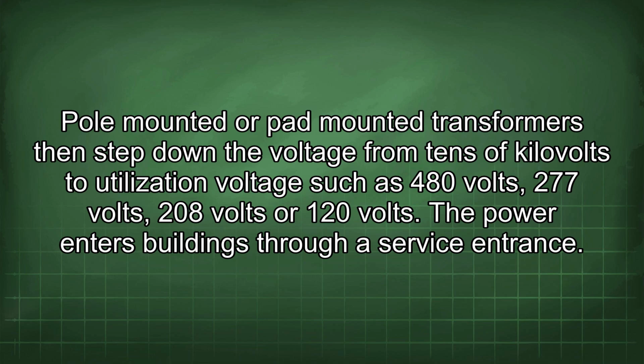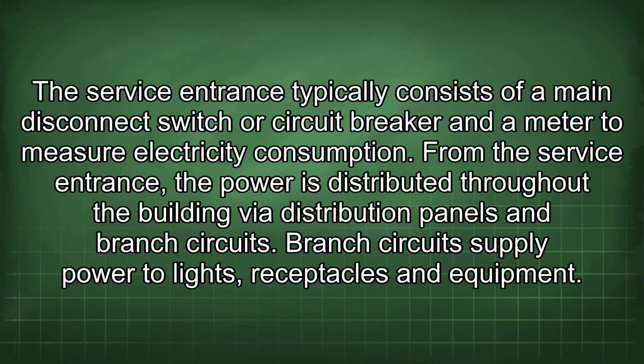Pole-mounted or pad-mounted transformers then step down the voltage from tens of kilovolts to utilization voltage such as 480 volts, 277 volts, 208 volts, or 120 volts. The power enters buildings through a service entrance. The service entrance typically consists of a main disconnect switch, a circuit breaker, and a meter to measure electricity consumption.